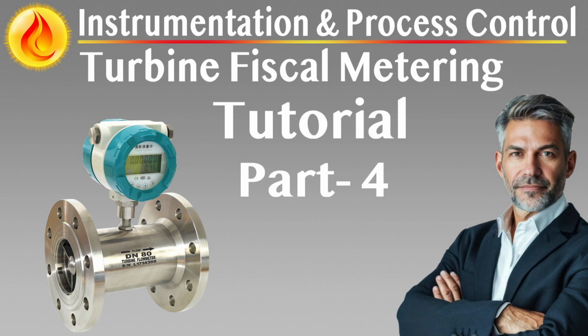The stream microcomputer must communicate with the station computer over a secure, high-reliability digital link. It must also support standard communication protocols for real-time data sharing with supervisory systems. Local alarm outputs must be issued in the event of meter failure, pulse loss, invalid parameter values, or flow detected while the stream is deselected.